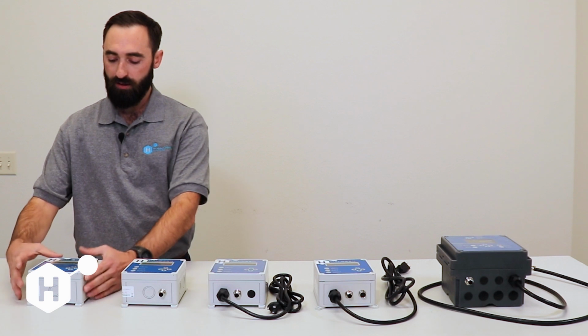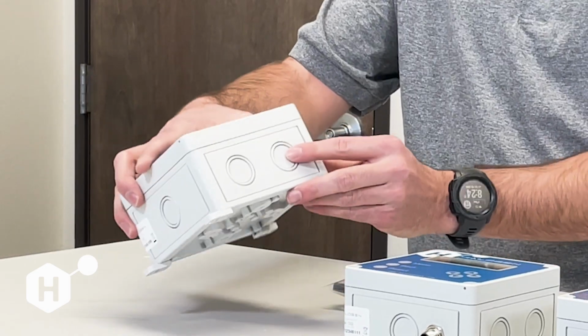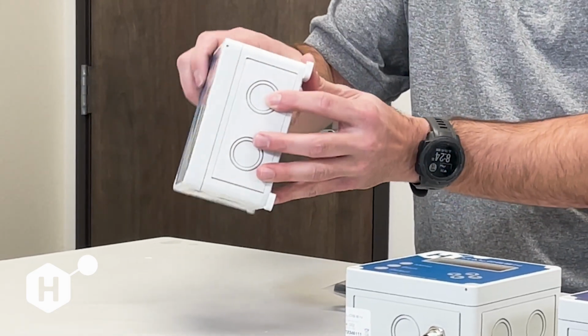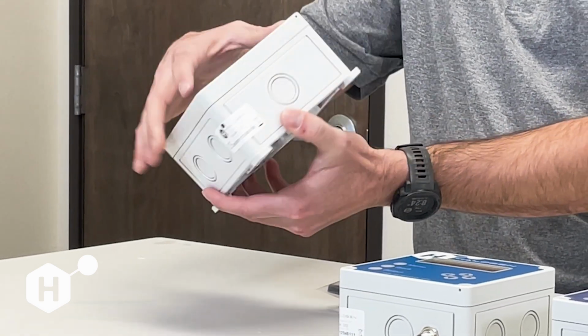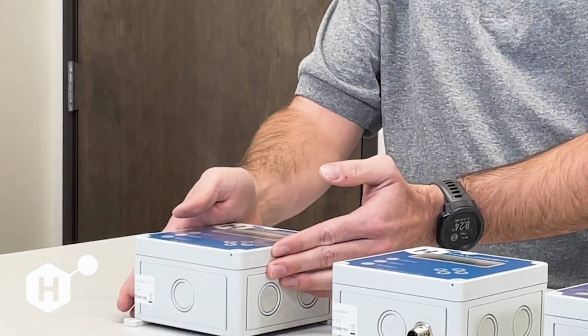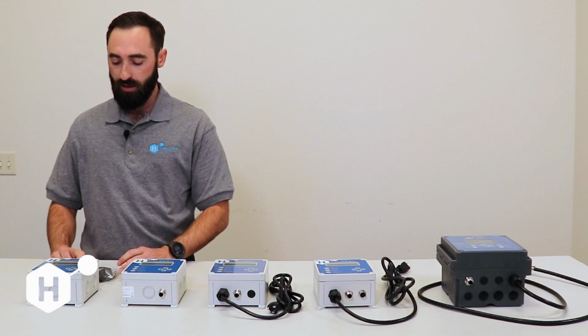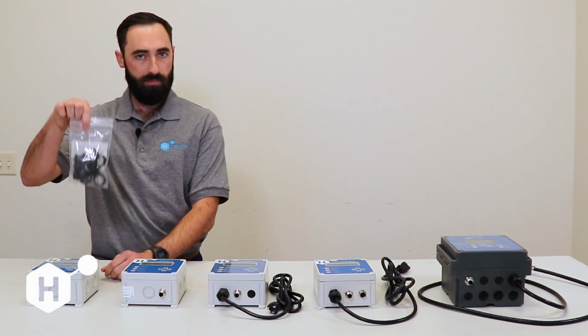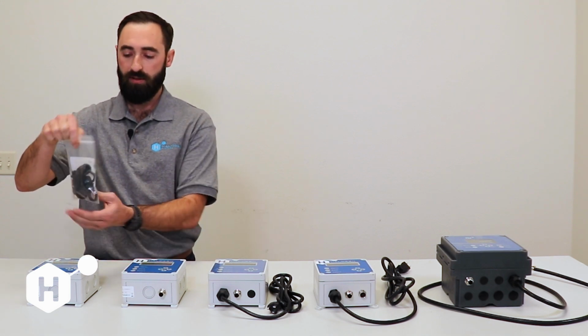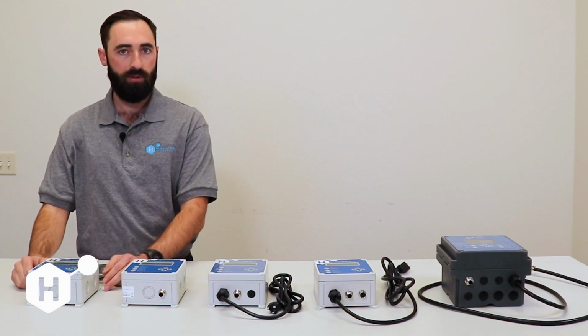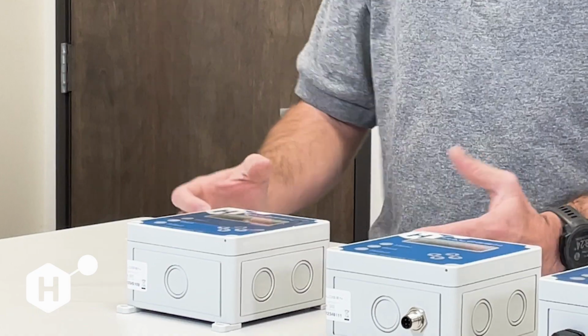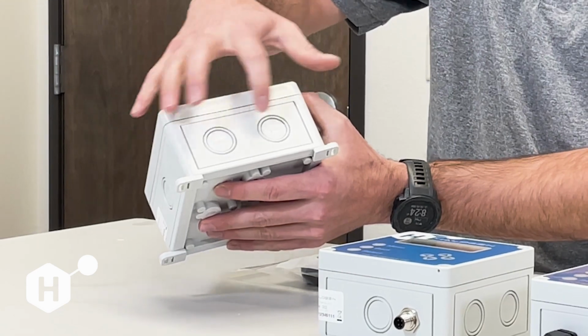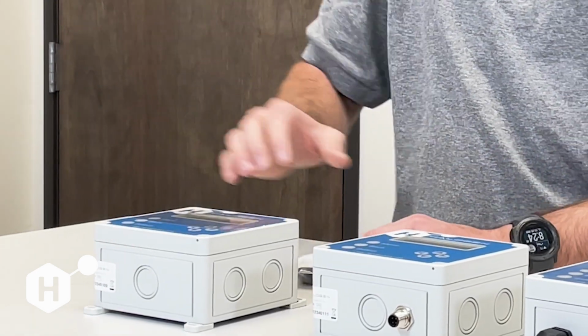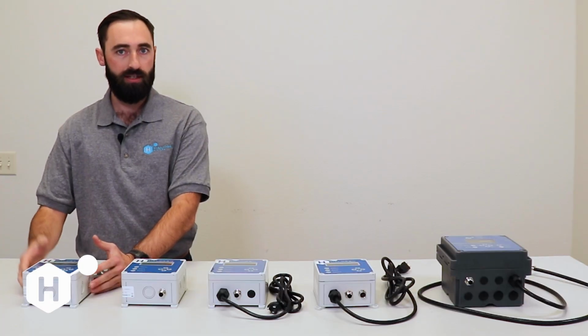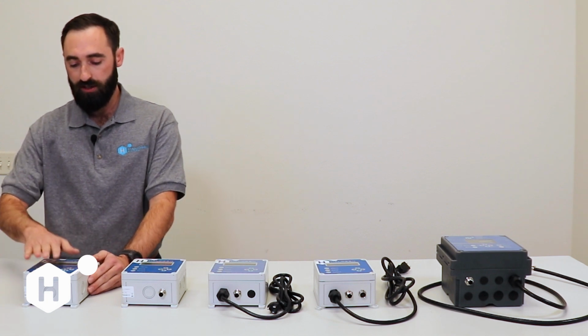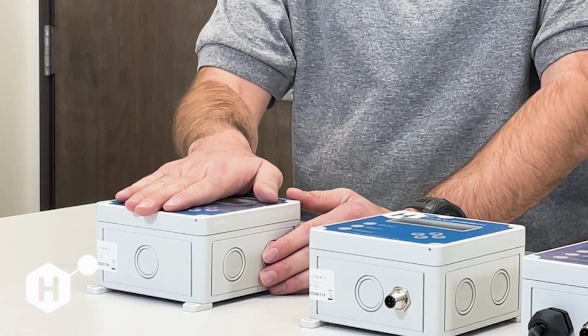That is supplied directly through one of these knockouts. Each one of these display enclosures has multiple knockouts for PG16 or PG21 size strain reliefs. We supply PG16 strain reliefs that accept 6 to 12 millimeter cable diameter. These can just be installed by knocking out the knockouts here and installing in whatever configuration you need to wire to your system. The D01 is our most basic display transmitter model.